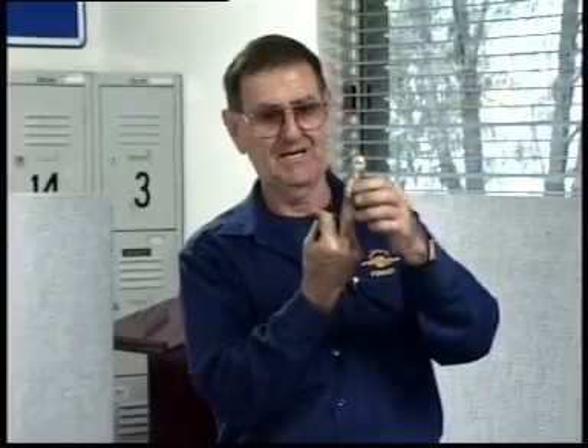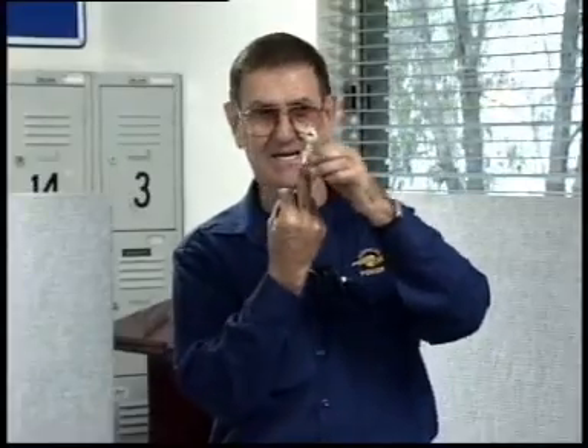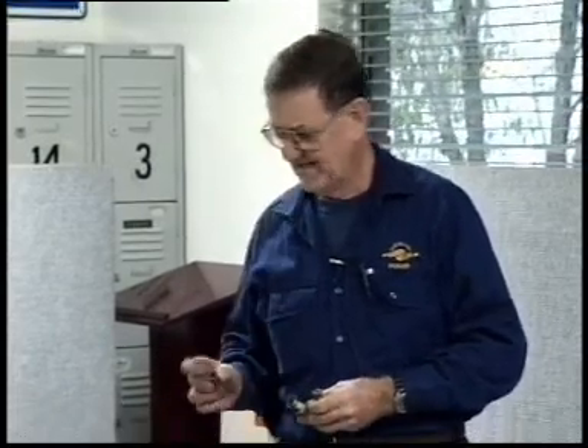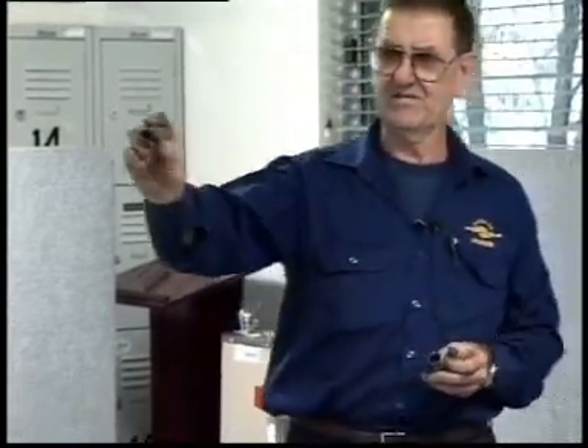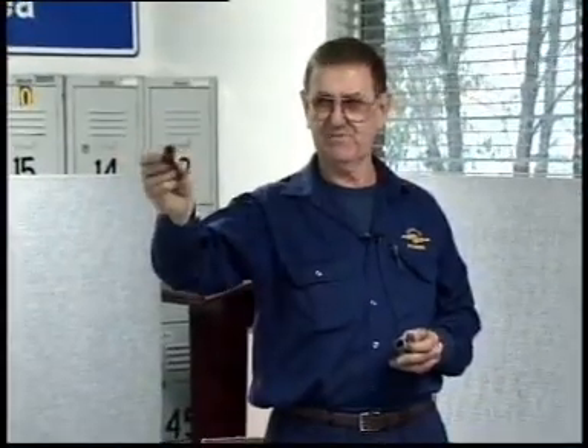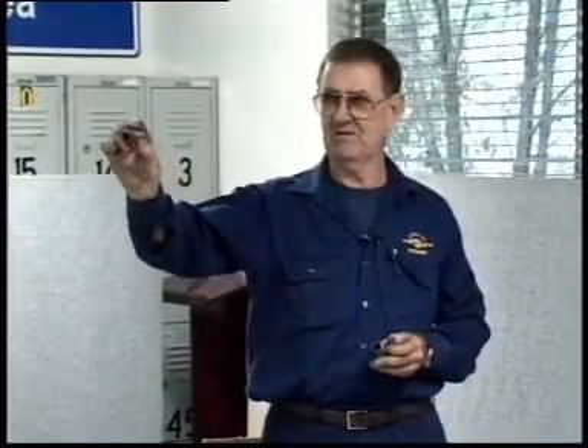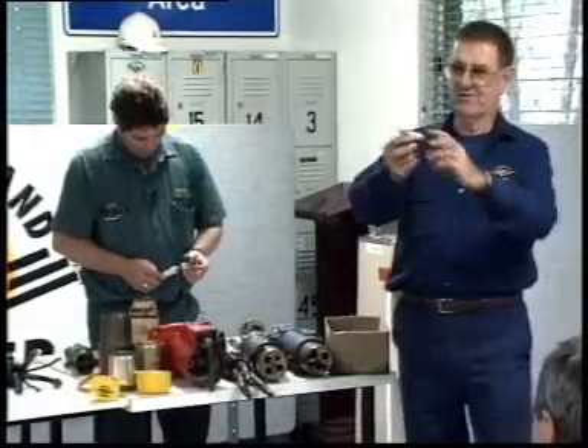Once it starts to heat up, it's like a dog chasing its tail. It then heats this up. Once it heats that up, the spring deteriorates further, and so on, until you get to the stage where you actually get burning down the inside of the contact altogether. And if you have a look at those, you'll see where the contact's actually burnt off. This particular one here never had a spring on it when it came into us, that one there, which we salvaged. On this one here, you'll find a little bit of burning on this tapered section.